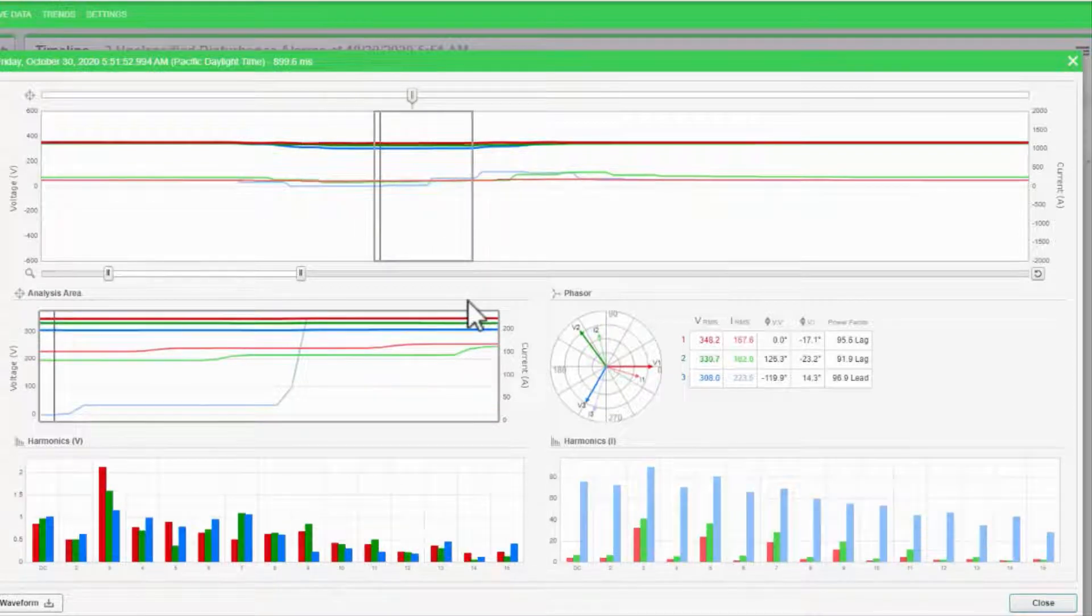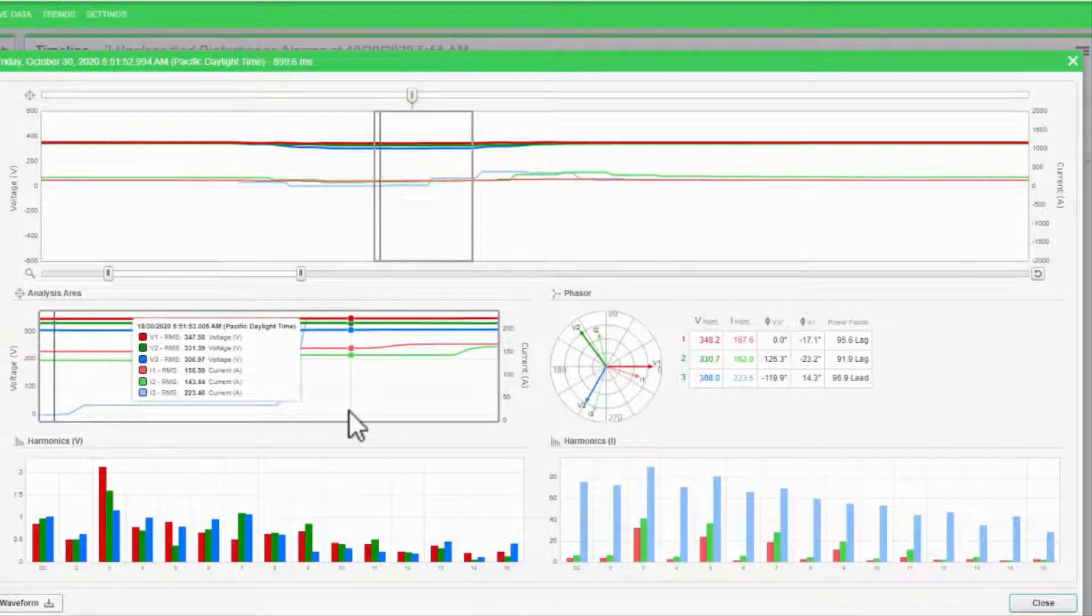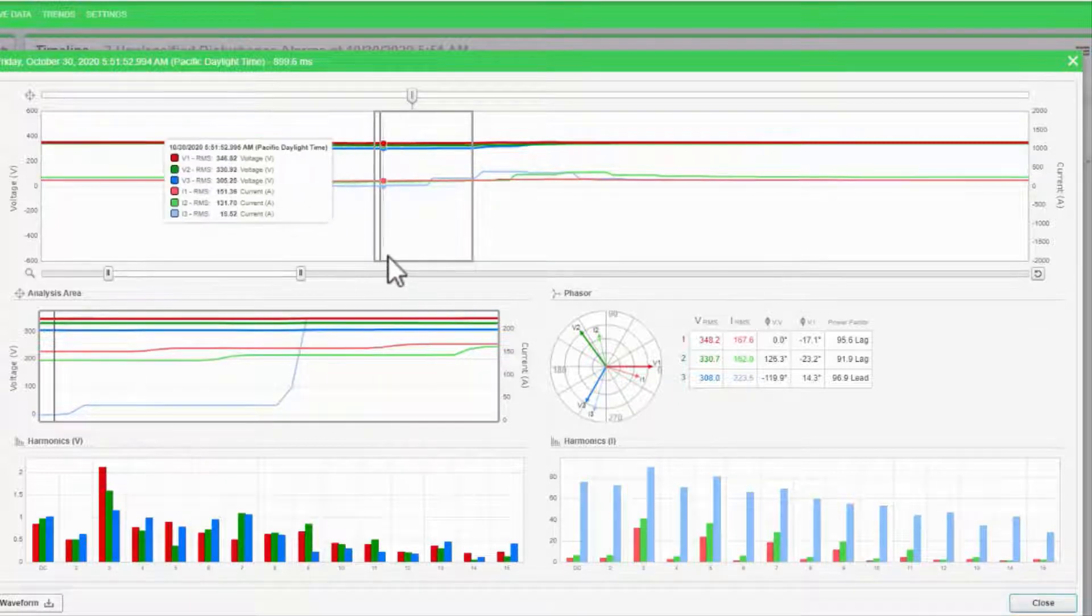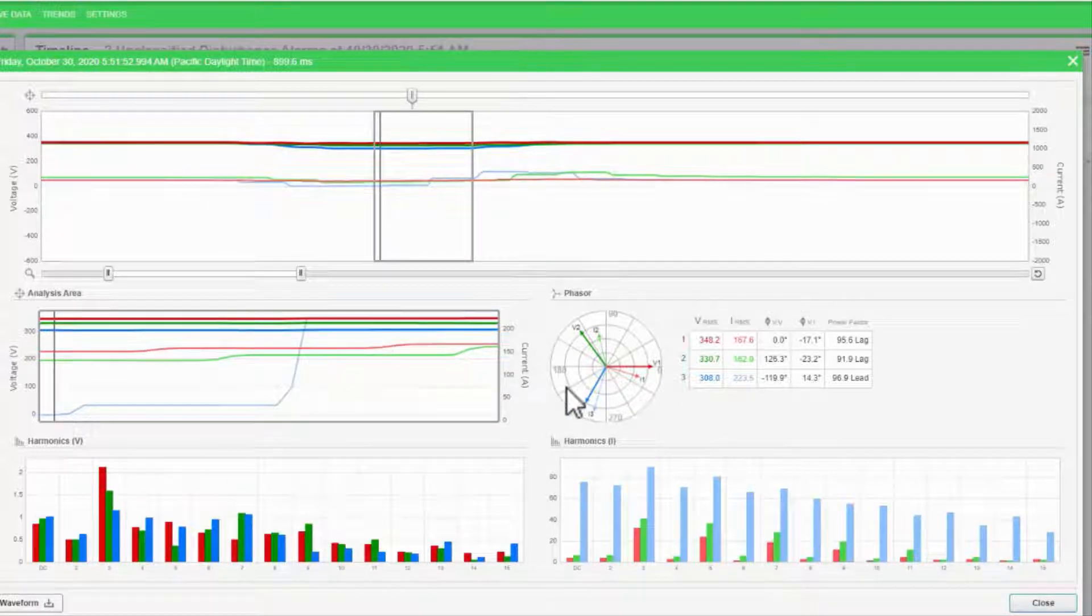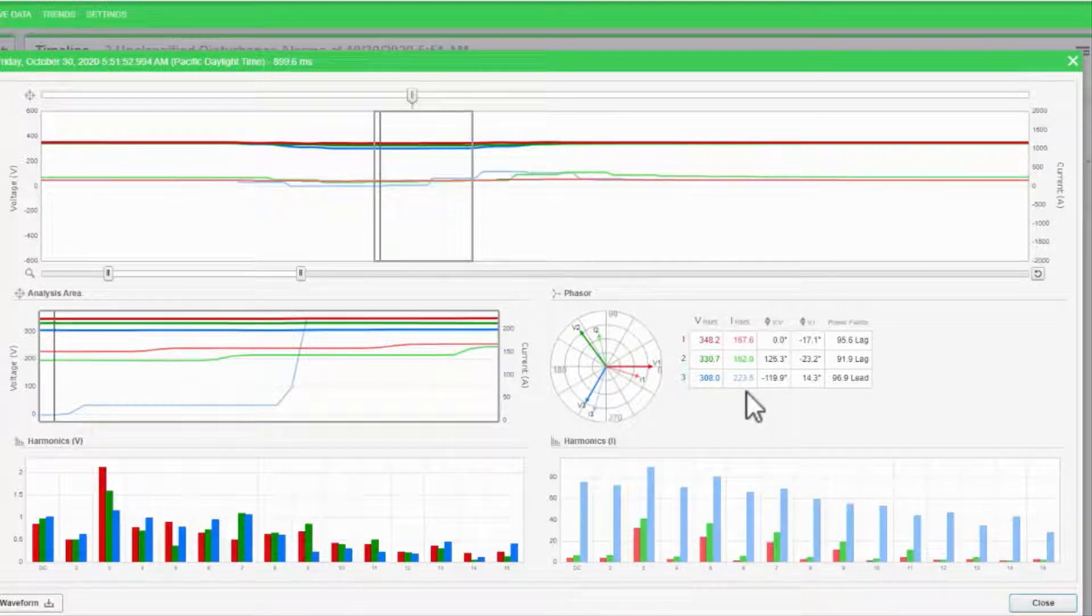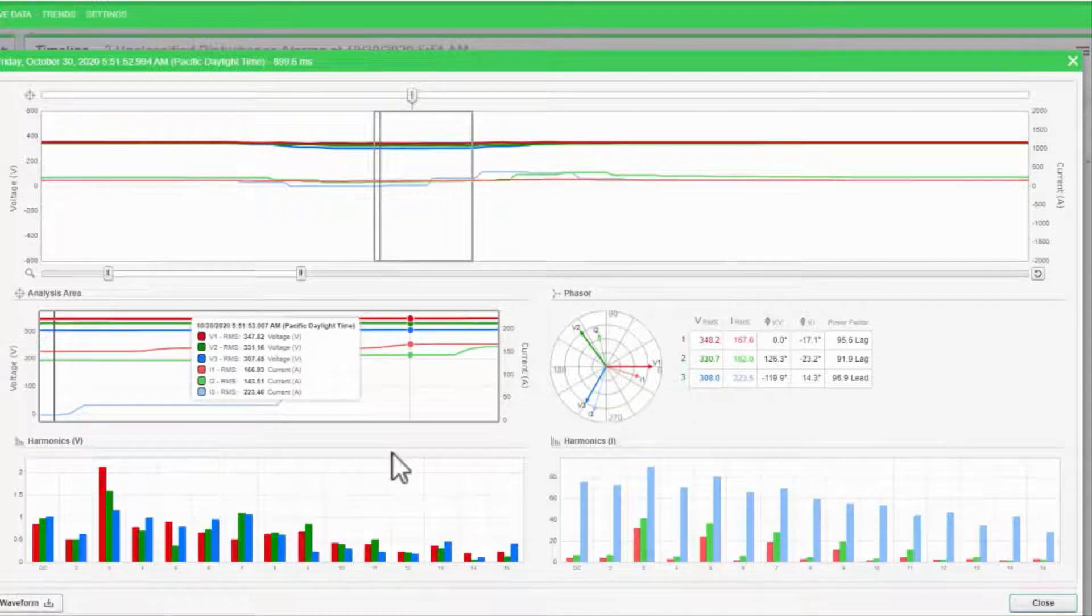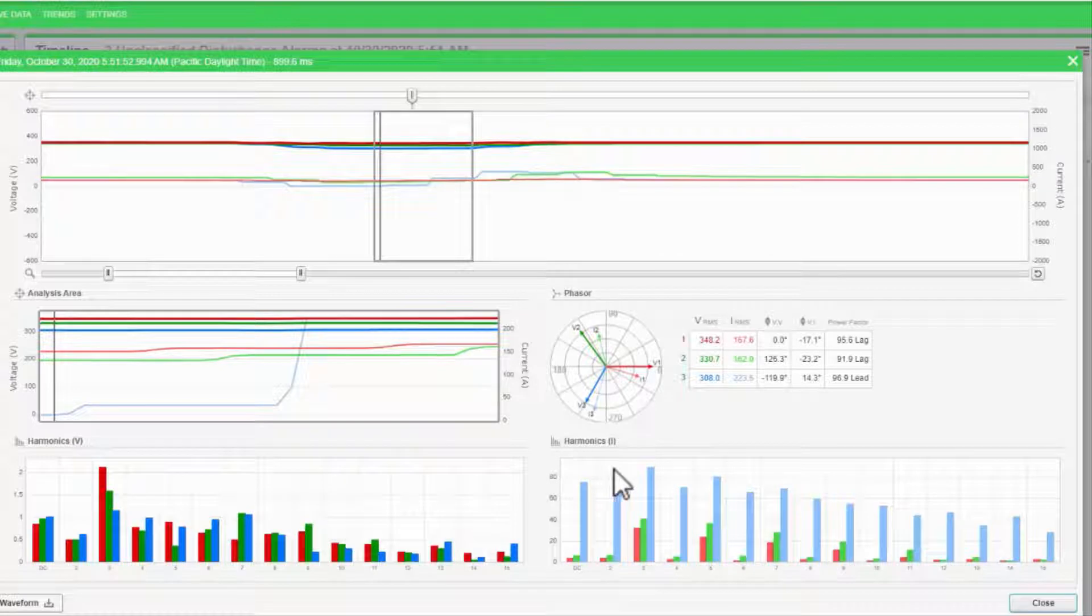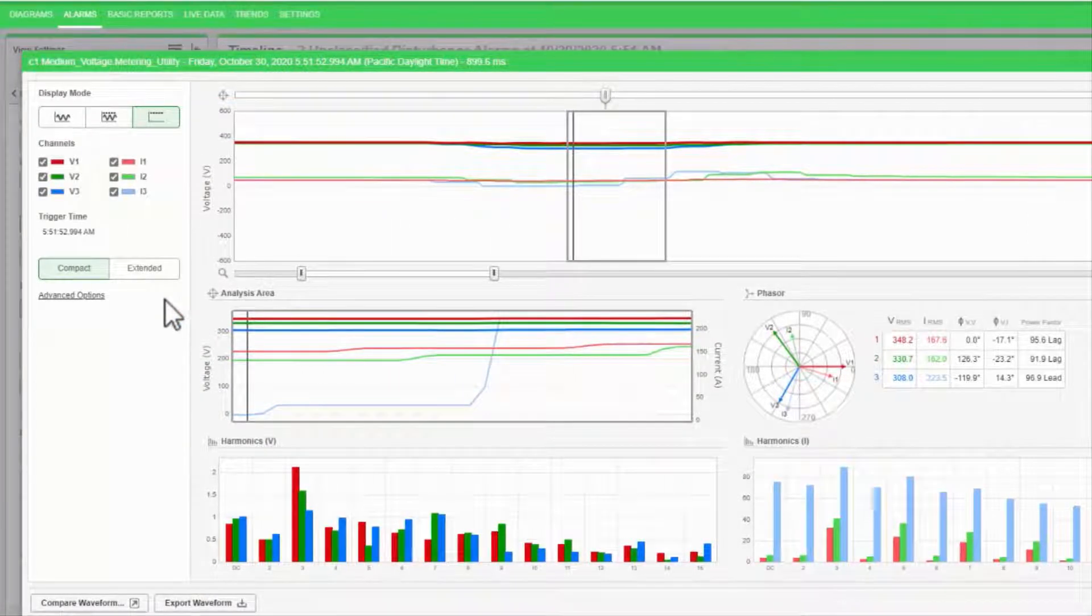Below, I have the analysis area displaying exactly what is contained in the window above. The phasor section gives me a phasor diagram as well as the RMS magnitudes and angles in the analysis window. I also have a map of the current and voltage harmonics measured in the window.